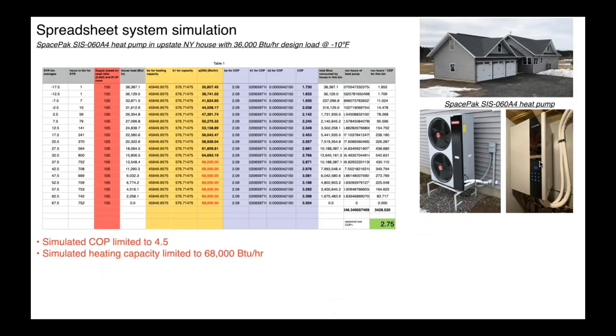Okay, now I ran another one. If earlier this year you tuned in on some of the mini-series that we did, I talked about a project that I was involved with pretty extensively last summer with my daughter, building a new house. And we actually put this SpacePak unit in. So I just took the spreadsheet and I modified it a little bit. How's this house going to perform with that same heat pump? Well, this house has a significantly lower load, design load of 36,000 BTUs per hour at a minus 10 outside temperature.